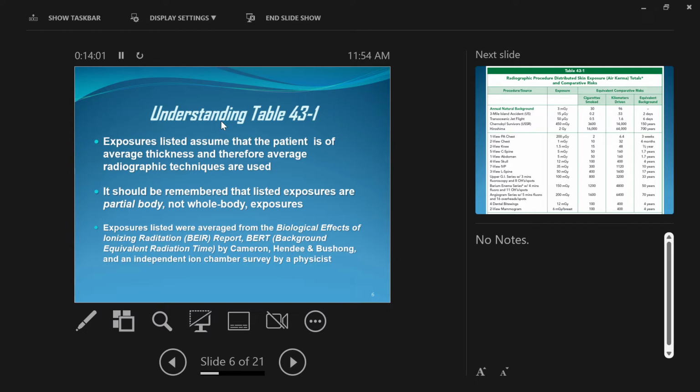So the first one is called kilovoltage peak, and it's given as just a three-letter acronym, kVp. Little k, I should probably draw the k, more like a little k. Okay, little k, capital V, lowercase p. kVp. This controls the X-ray beam energy, okay?